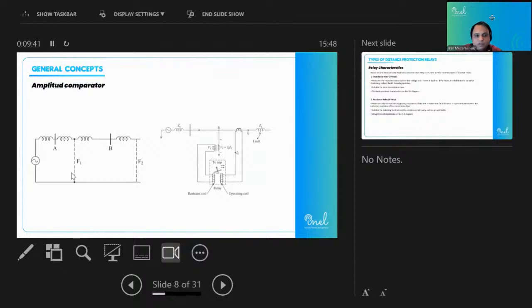But now there is another quantity, which is the operating quantity. If at point A, say at this point, we are going to connect a relay, then the voltage at this point and the current at this point will decide the impedance of this transmission line. So if that measured impedance is greater than the transmission line impedance, then this is a normal operation for the transmission line. But if this measured impedance is less than the actual impedance of the transmission line, then the relay will consider it as a fault.